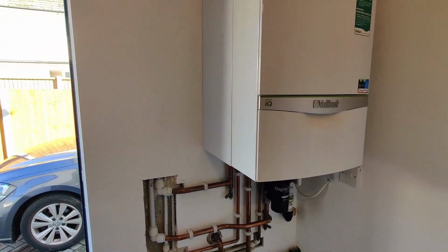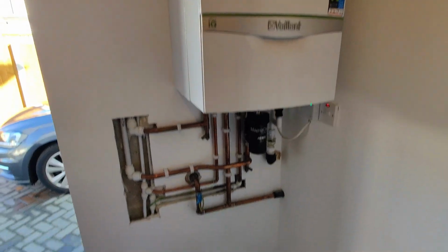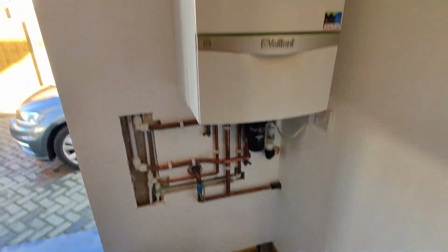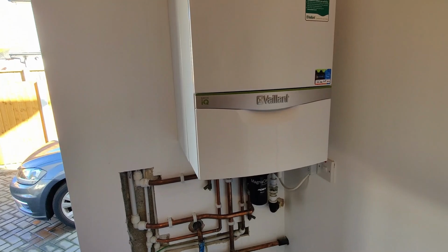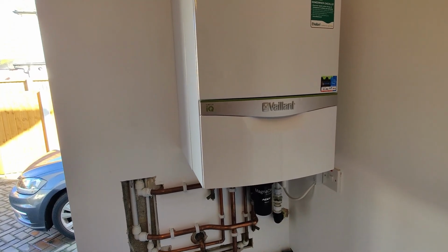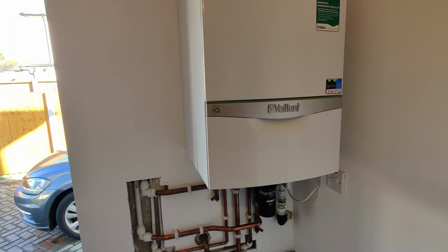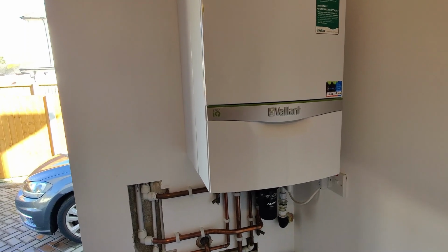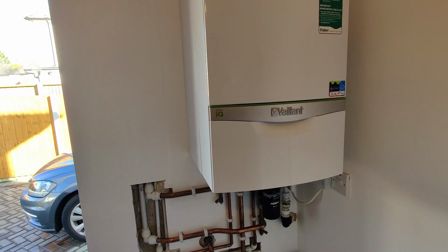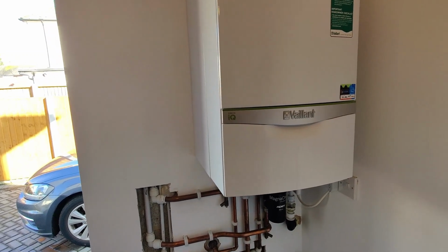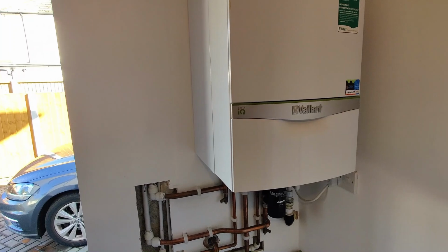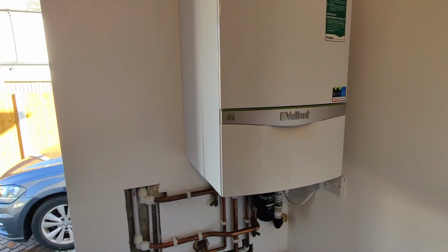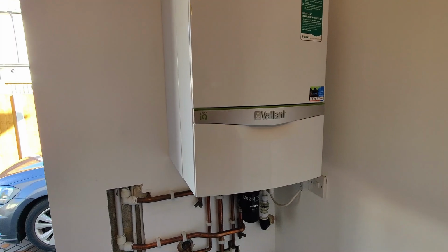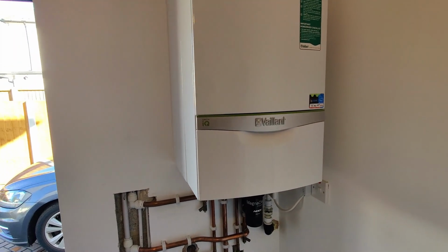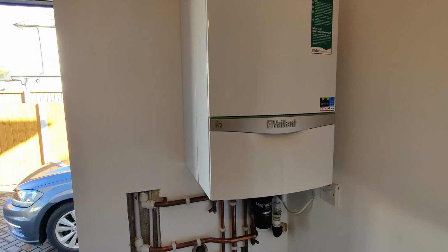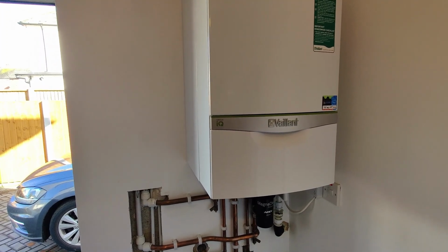Checked the inhibitor level and water quality. Inhibitor level was very low, so I topped it up. And that's about it really. Everything else is working perfectly fine. It's only a 3 year old boiler, in fact 2022 to 2024, a 2 year old boiler. I think it was February 2022 when it was installed, if I remember correctly. So it doesn't require the whole combustion chamber opening up and burner inspections and stuff like that. Readings are perfectly fine.